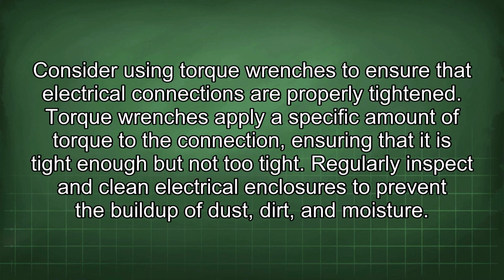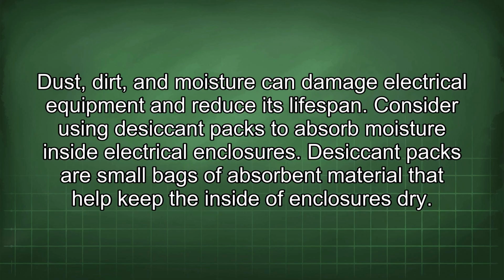Consider using torque wrenches to ensure that electrical connections are properly tightened. Torque wrenches apply a specific amount of torque to the connection, ensuring that it is tight enough but not too tight. Regularly inspect and clean electrical enclosures to prevent the buildup of dust, dirt, and moisture. Dust, dirt, and moisture can damage electrical equipment and reduce its lifespan. Consider using desiccant packs to absorb moisture inside electrical enclosures. Desiccant packs are small bags of absorbent material that help keep the inside of enclosures dry.